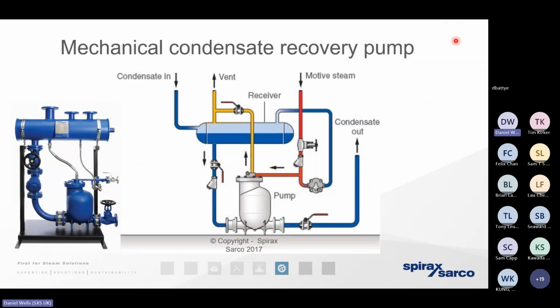Of course, there are certain areas where we're never going to have enough motive energy present within the steam. We need to pump it in some way. And we can do that mechanically. It's basically the big brother of that automatic pump trap. We're using steam to pressurize the condensate, so there's no electrical installation required. But the pump takes time to pressurize. So it's actually only going to be discharging condensate 25% of the time, because the rest of the time it's either filling the pump chamber, pressurizing it, or discharging that motive steam to atmosphere. Works like your toilet system at home. It's slow to fill, rapid to discharge.